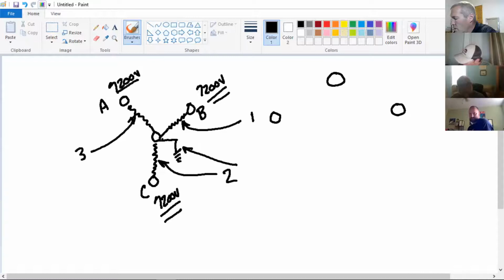The special thing to look for on a system is what I'm using here - a grounded neutral at the bottom. This is how you can distinguish, just by looking at a power line, whether it's a Y configuration or a delta configuration. How many phases do I have? Three. Do I have a neutral? Yes. Is it grounded? Yes. That's a Y configuration.